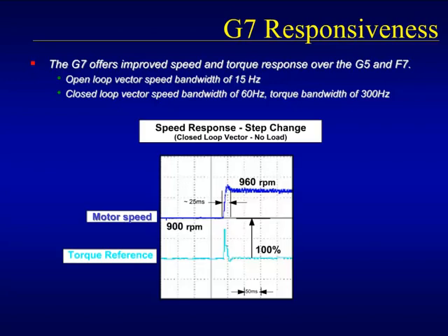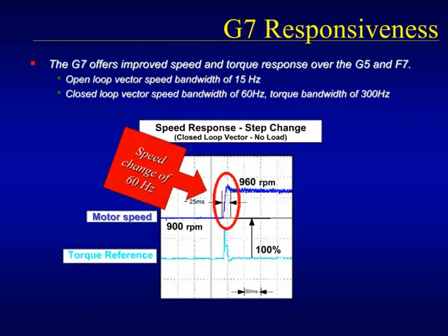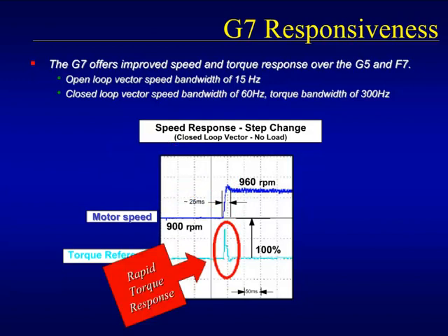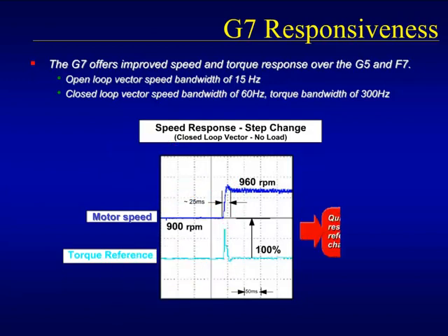This slide shows a scope trace of the G7 responding to an instantaneous change in the frequency reference, or a step change. A change of 60 RPMs is achieved in approximately 25 milliseconds because of the G7's ability to rapidly achieve a very high torque reference.